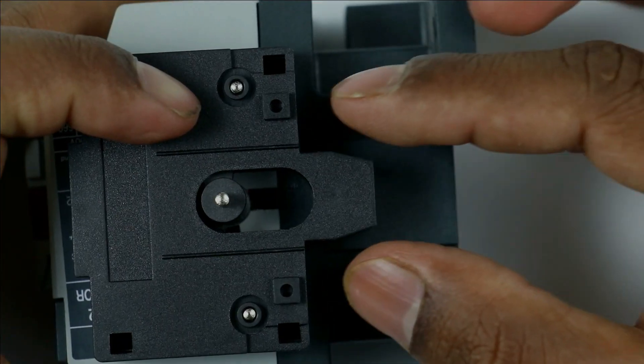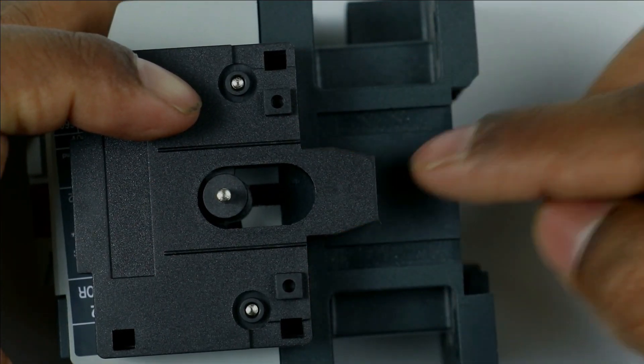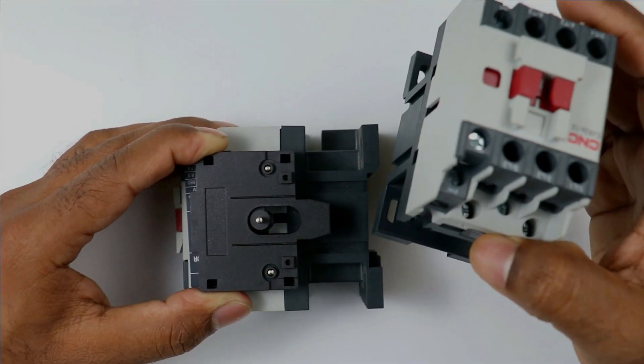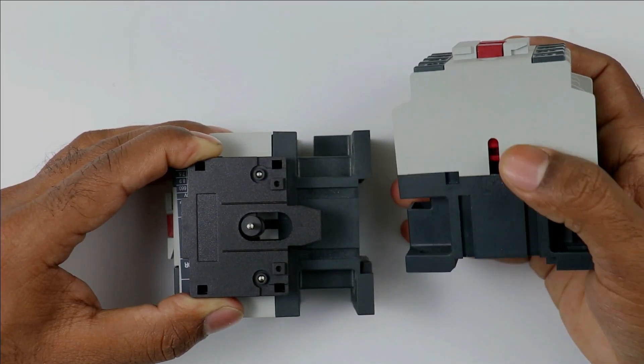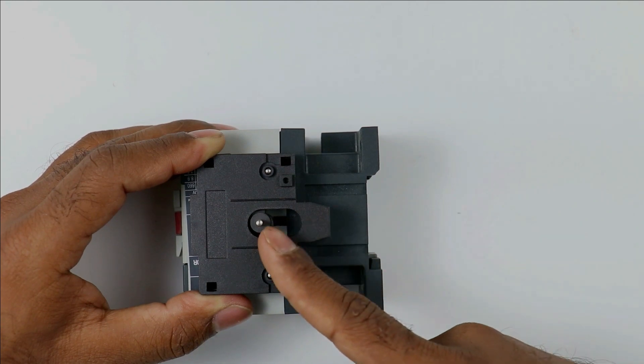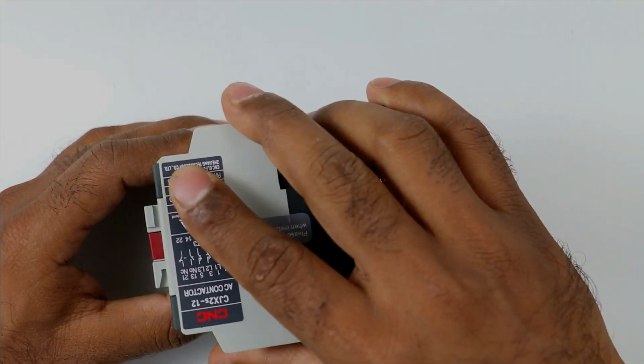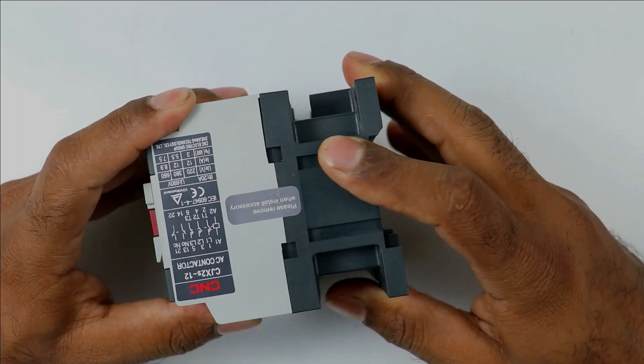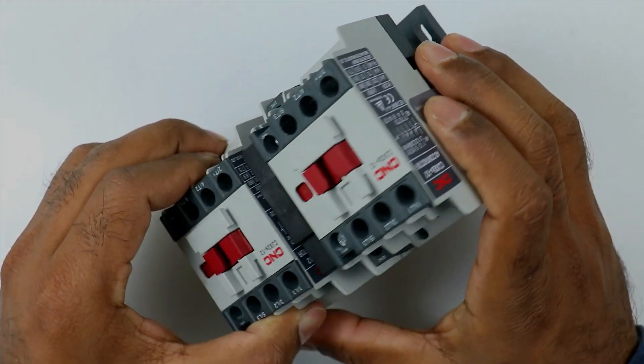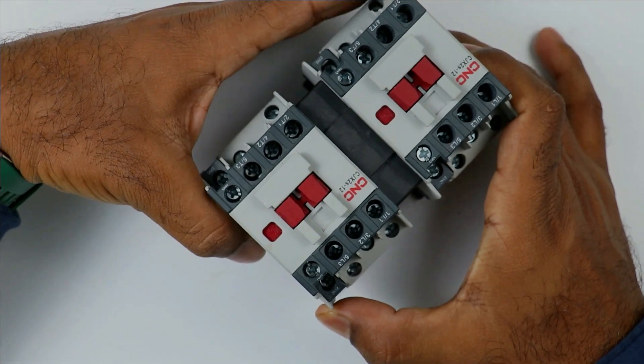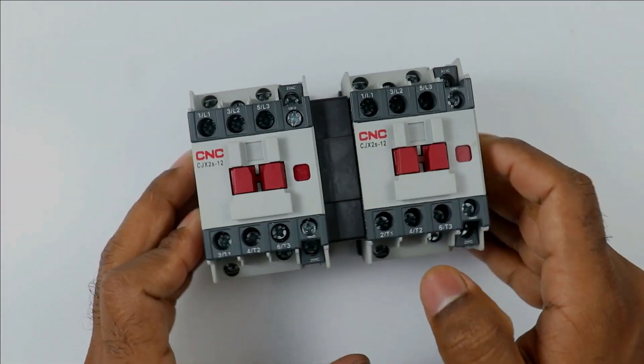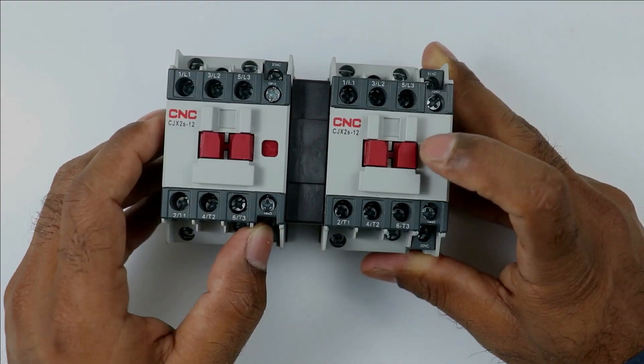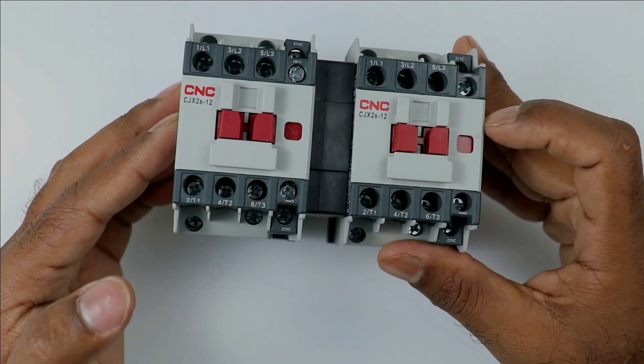Keep one thing in mind, this side should be downwards, at the upper side it should be flat. Take the other contactor and look at this side. After removing the sticker, mount the contactor with this lever present here. So I am mounting this. I mounted both of the contactors on contact. I will still not remove my hands on contactor to check whether it is perfectly interlocked or not. Both the contactors are making proper movement. So we mounted it perfectly.